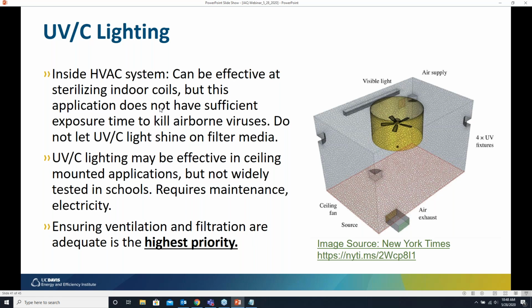Last note here about UVC lighting. There have been a lot of questions about this. UVC is a shortwave ultraviolet energy that's used to inactivate viruses and bacteria. One option is to install it inside of an HVAC system. So I want to caution you, this can be effective at sterilizing indoor coils, but it generally does not have sufficient exposure time to kill airborne viruses because the air is moving past that light at a very high speed. And so you would need extremely high power densities in order to be effective inside an HVAC system.